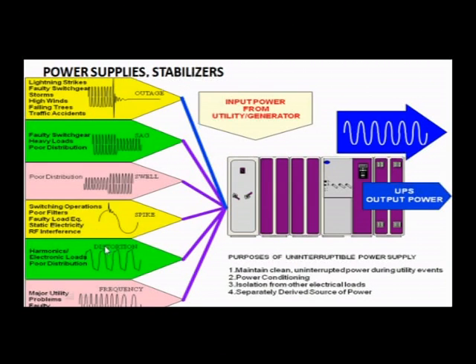One slide I wanted to show clearly so you understand the purpose of a UPS. The UPS output shown here is a pure sinusoidal waveform, and this is the input power, the utility power input. So the purpose of UPS is to maintain clean, uninterrupted power during utility events - power conditioning takes place, there is isolation from other electrical loads, and it is a separately derived source of power.